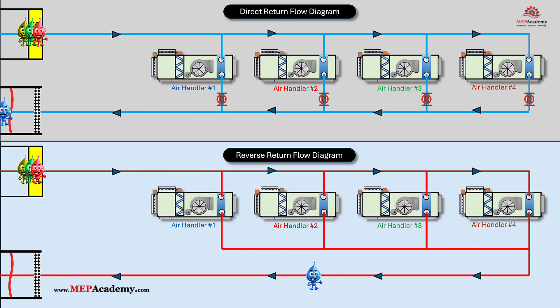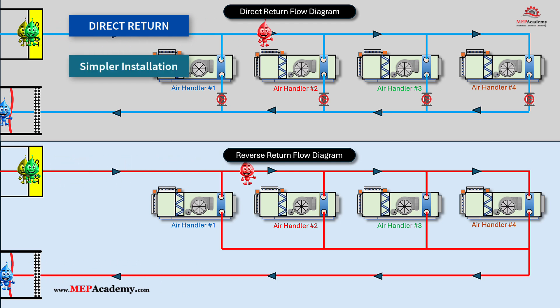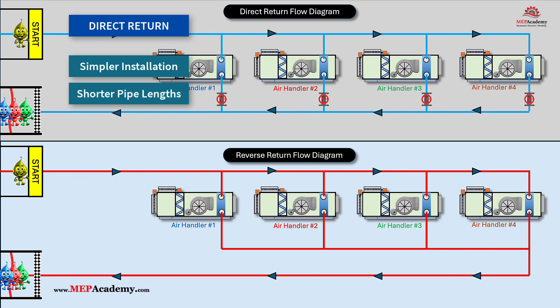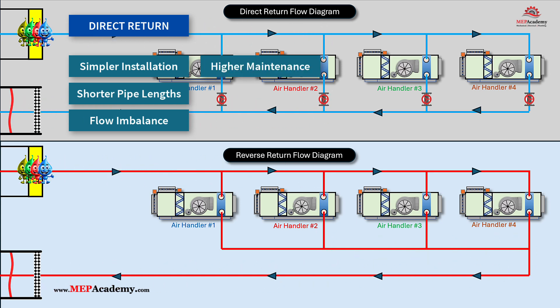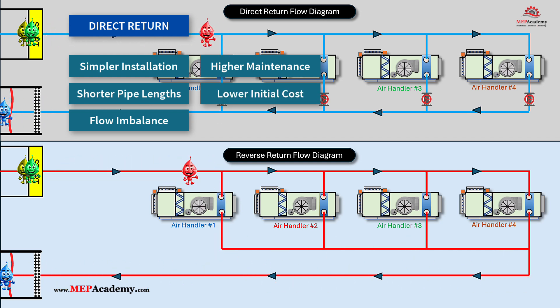Here are the main ideas to remember about direct return vs. reverse return piping systems. Direct return piping: simpler installation — main pipes stay the same size until a reduction is necessary, streamlining material handling and installation. Shorter total pipe length typically requires less piping, saving on material costs and installation time. However, unequal pipe lengths to each terminal unit create varying flow resistances, making water balancing more challenging. More frequent adjustments and use of balancing valves are needed to ensure consistent flow rates. Lower initial cost — installation is generally less expensive due to reduced pipe material and labor.